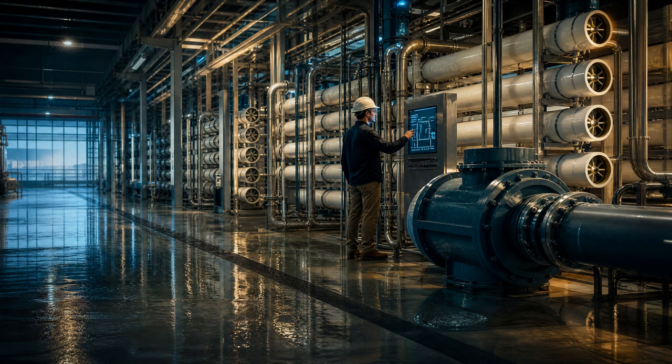Energy is often the first metric used to discuss low-carbon desalination. The International Energy Agency reports an approximate range of 2.5 to 6 kilowatt-hours per cubic meter for seawater reverse osmosis, including basic steps. This range is useful as context, but it must not be presented as a universal plant value or as a performance guarantee.